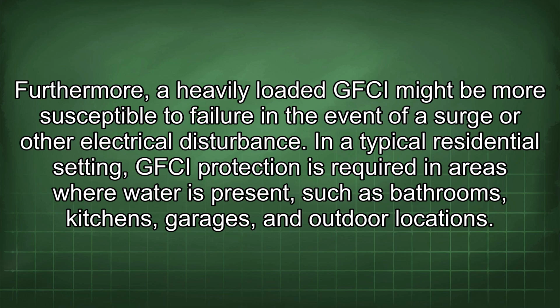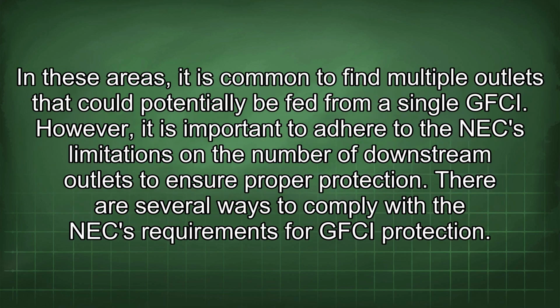disturbance. In a typical residential setting, GFCI protection is required in areas where water is present, such as bathrooms, kitchens, garages, and outdoor locations. In these areas, it is common to find multiple outlets that could potentially be fed from a single GFCI. However, it is important to adhere to the NEC limitations on the number of downstream outlets to ensure proper protection. There are several ways to comply with the NEC requirements for GFCI protection.